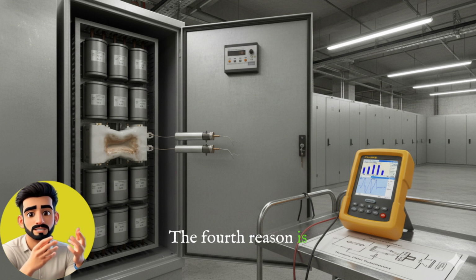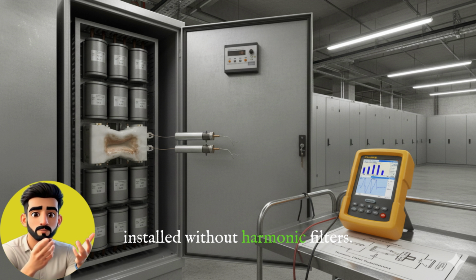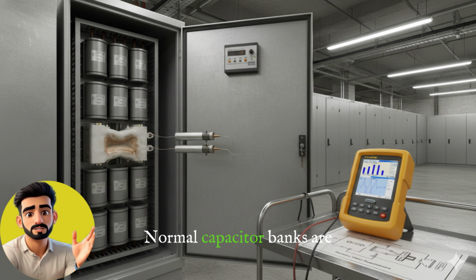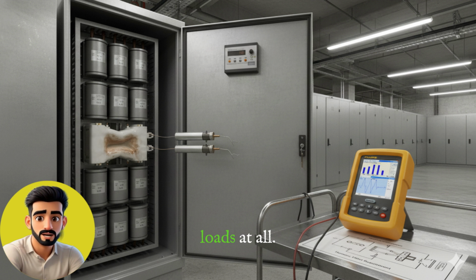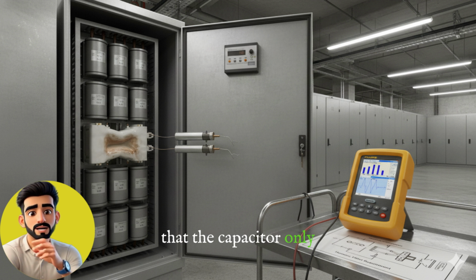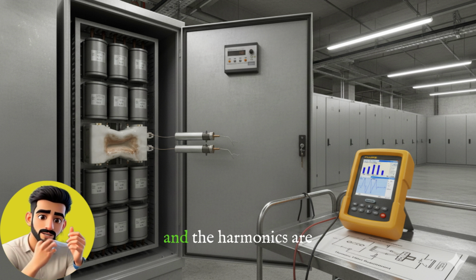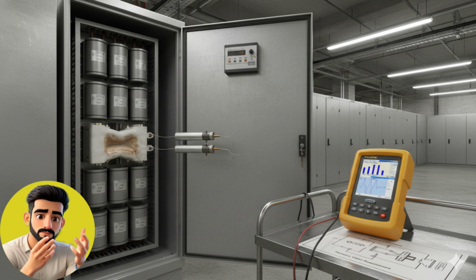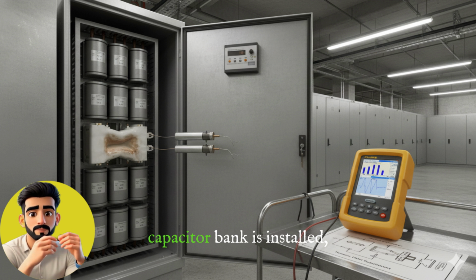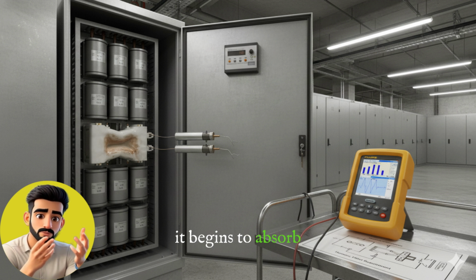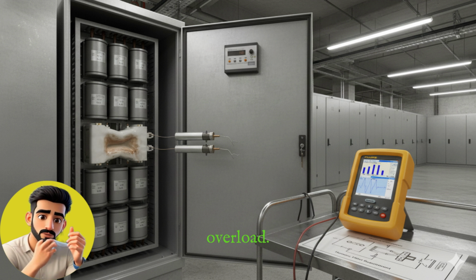The fourth reason is that capacitor banks are installed without harmonic filters. Normal capacitor banks are not safe for harmonic loads at all. In such plants, it is necessary to install the harmonic filter capacitor bank in series so that the capacitor only handles the main frequency and the harmonics are diverted to the filter. If only a plain capacitor bank is installed, it begins to absorb harmonic currents, leading to overload.